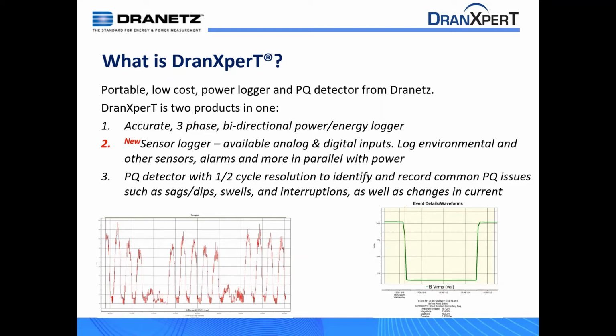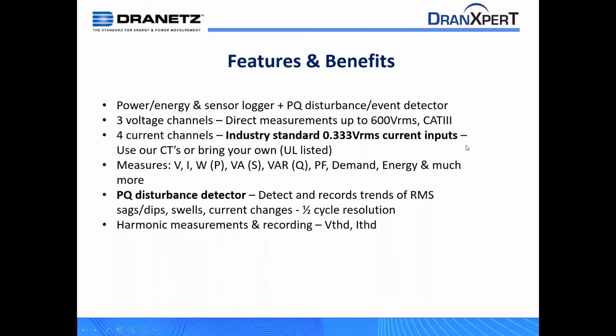You probably want to pull out a more advanced Dranetz product like our HDPQ family to go identify and resolve that particular issue. So although there's many characteristics of the power quality capabilities, such as half cycle resolution, that are shared with our PQ meters, this is not in compliance with any PQ standards. It just happens to follow some of the methodologies. So the main features and benefits of DranXperT, again, it is a power/energy, both sensor logger and PQ disturbance detector all in one. You choose what you want to enable. You can do all of them or any one of these separately.